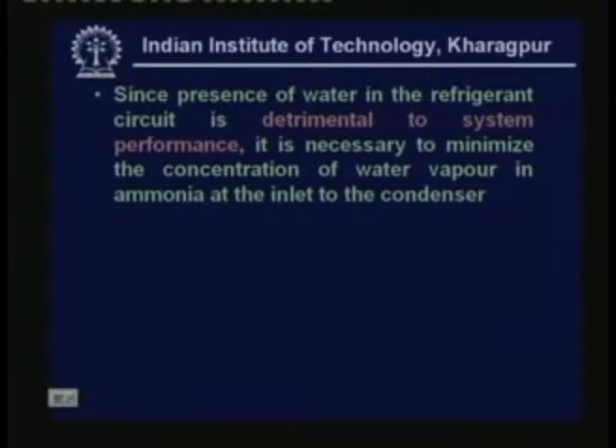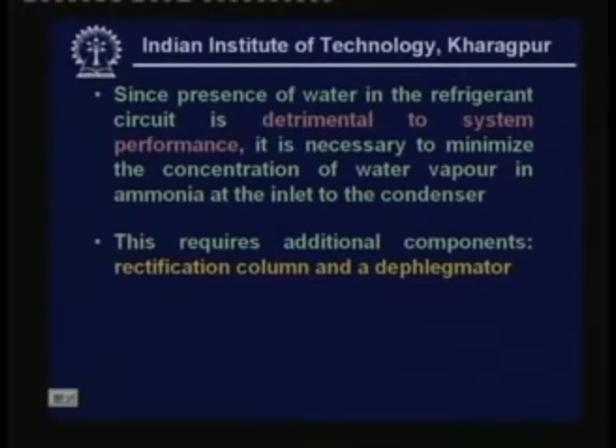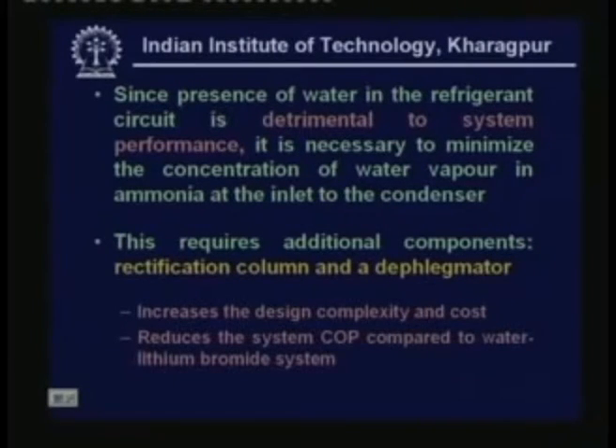So what we have to do is minimize the concentration of water vapor in ammonia at the exit of the generator or at the inlet to the condenser. We have to ensure that almost pure ammonia vapor goes to the condenser. This requires additional components — namely a rectification column and a dephlegmator. As a result, the design of ammonia water systems is more complicated and the cost is higher. Additionally, due to these additional components, the system COP is also reduced when compared with water lithium bromide systems. These are the main differences between the two systems.